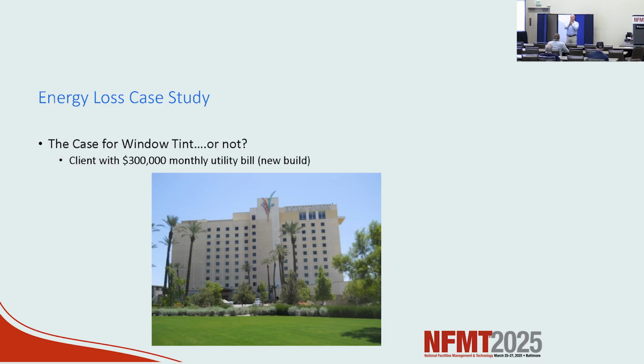So guess what? The glazing sections were between 20 and 30 degrees hotter than the non-tinted windows. I did all the thermal investigation with a camera and thermocouples, and I was able to come back and say, not only is tint the worst thing you can ever do, guys, but every single one of your windows in the hotel has already failed.